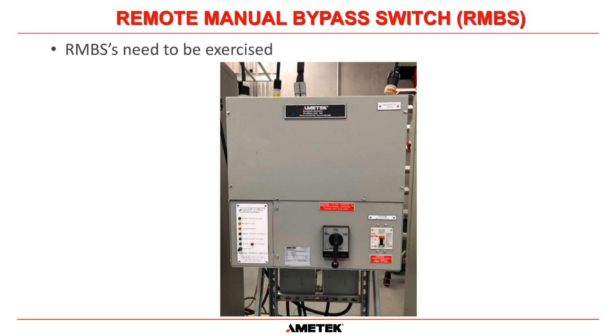Now, another thing that people don't realize is that remote manual bypass switches need to be exercised. If you never operate the switch on an RMBS, and then after 5 years you want to move it from normal position to bypass, then you could be asking for problems, because the contacts within that switch, because they have not been moved, could have oxidized slightly, could have seized. There are many things that can go wrong with a switch that never gets operated.